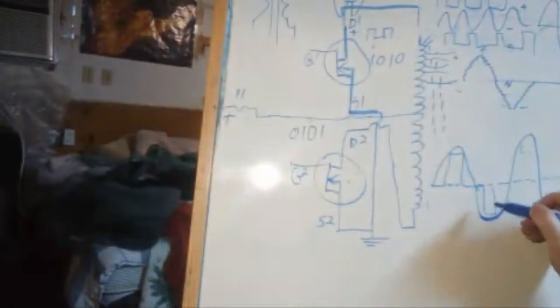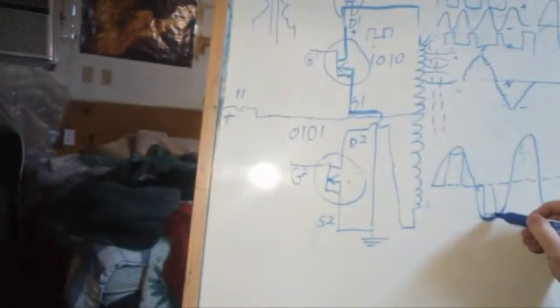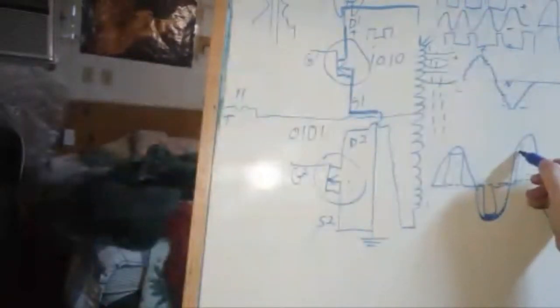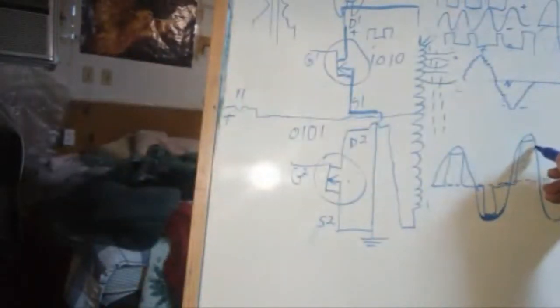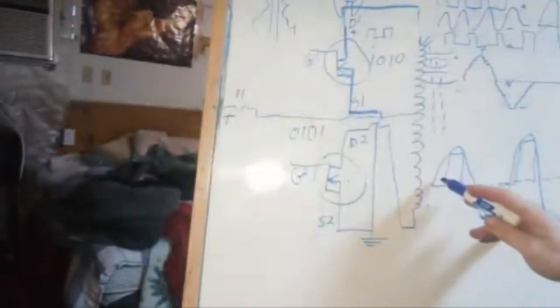It moves over, and it does actually go all the way down. This is also why, if you don't have what's called a true RMS meter, this will not be detected properly. I'm not going all the way up so you can still see the dotted line signifying neutral, and then it goes up, over, and then down. Now, do you notice how there's power that's not being used? There's a lot of power being lost, and just flat out not being generated.